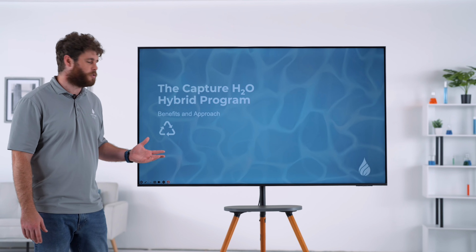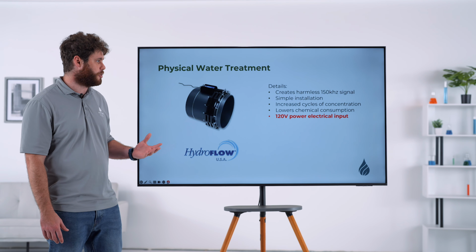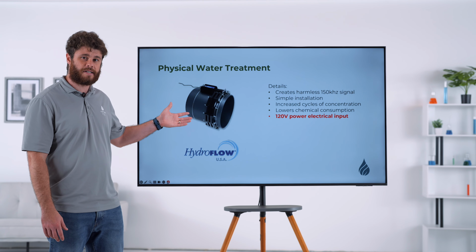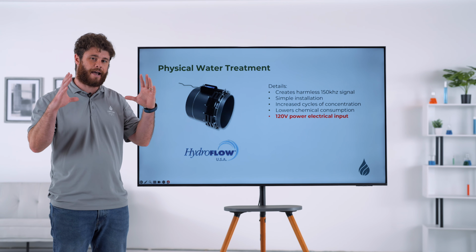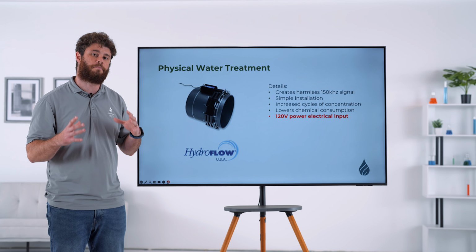So the hybrid program utilizes what's known as a physical water conditioner. It's this device here. You can see it mounts on the outside diameter of your condenser open loop piping. And this device will act as your mechanism for controlling scale, corrosion, and bacteria with limited chemical supplementation.